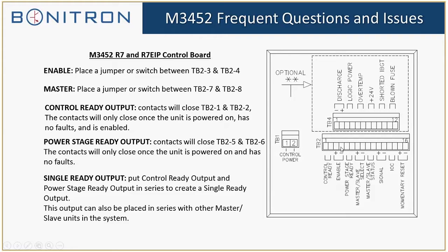The control ready output, this basically is a dry contactor. It's a normally open but held closed contact. So that means whenever there's a fault or the unit's not enabled, the control ready contact will open. There's also the power stage ready. The reason we have two separate ready outputs is that customers may want to know that their unit's functioning without it being enabled. So that's why we have the power stage ready. The power stage ready basically tells that the IGBT and all the other power stages are fine and functioning well.